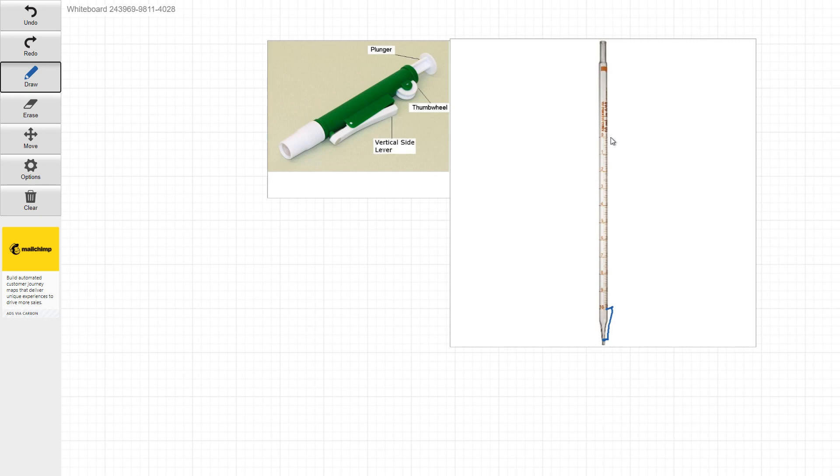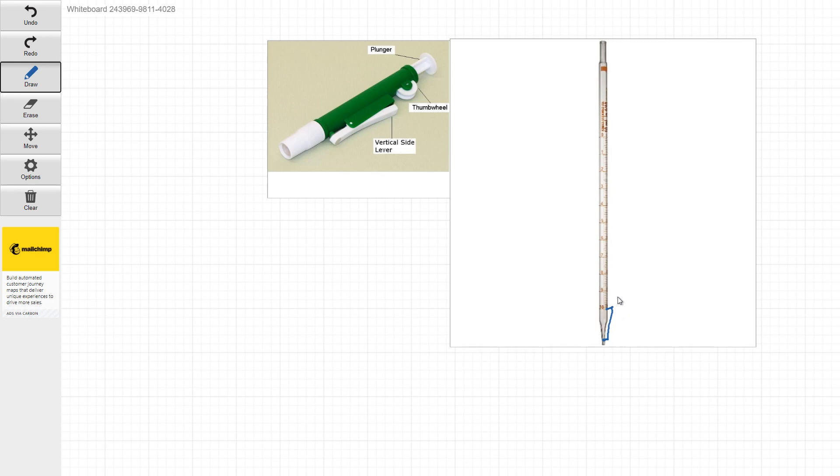And again, for this case, we want to go to 10, you go from zero to 10 and you stop here, you don't empty this out. So if you guys do empty this out, you will mess your measurements up and you'll see that it'll throw the readings off.